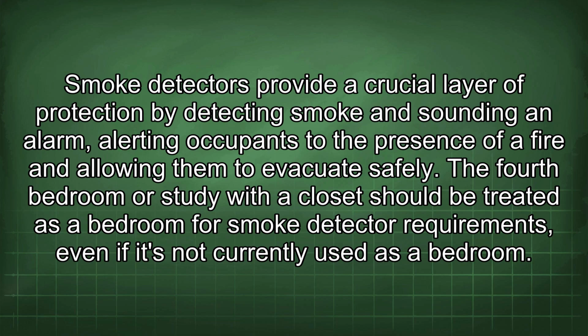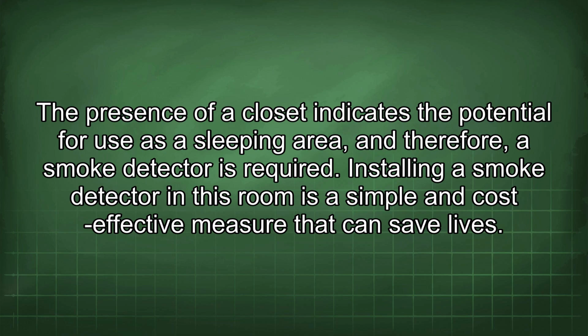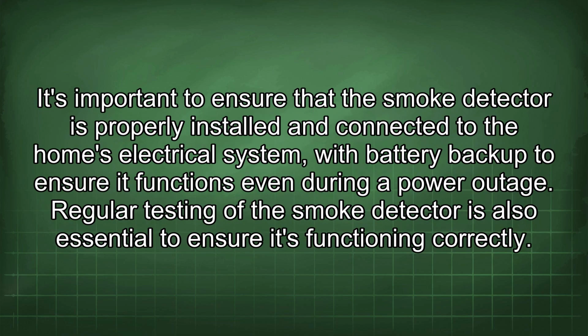The fourth bedroom or study with a closet should be treated as a bedroom for smoke detector requirements, even if it's not currently used as a bedroom. The presence of a closet indicates the potential for use as a sleeping area, and therefore a smoke detector is required. Installing a smoke detector in this room is a simple and cost-effective measure that can save lives. It's important to ensure that the smoke detector is properly installed and connected to the home's electrical system with battery backup to ensure it functions even during a power outage.